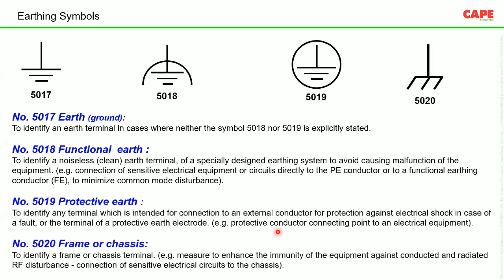So understanding the earthing requirement in a medical area is a little bit critical. It is a little bit technical as well. But you know what I am showing in the picture, 5017, 18, 19, and 20. These are called the earthing symbols, which is mentioned in the appliance. The appliance manufacturer should take care of his requirement, and the appropriate marking must be made. The installer or the designer of that particular location has to understand the meaning and the method of making the earthing, and he should make it.